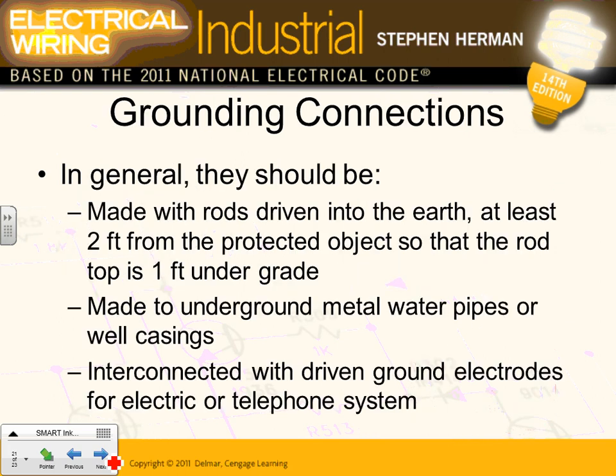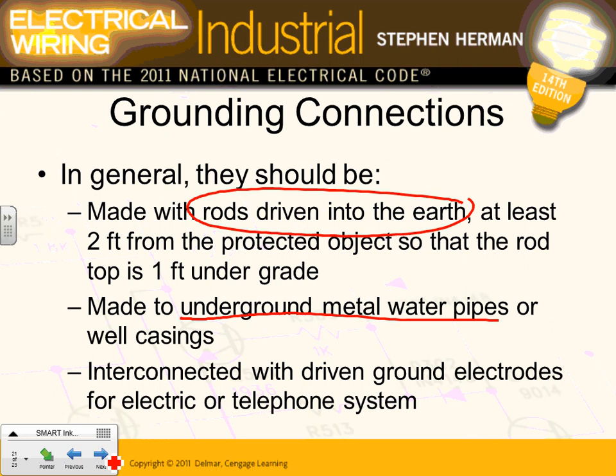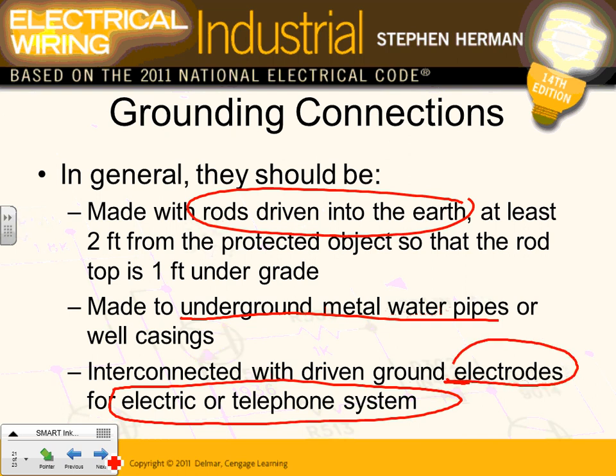For grounding: rods are driven into the ground — typically 3/4-inch by 10-foot rods — at least two feet from the protected object, with the rod top about a foot under the ground. You can also use underground metal pipe casing as your grounding electrode. Most importantly, you interconnect your grounding electrode system for the building's electrical utilities with your grounding electrode system for the lightning. All will be interconnected with at least a number 6 conductor.